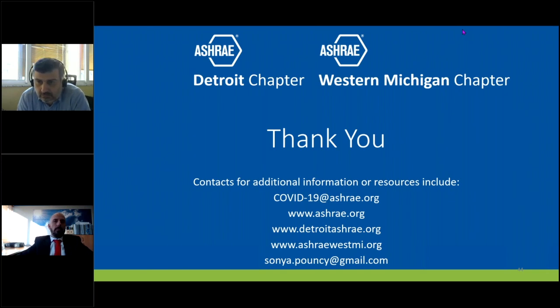If you can, field calibrate them, that would be good. You may reach out to, here in Michigan, we might use one of our test and balance or test adjustment contractors, who might be able to do something like that, or we would send out a calibration service provider to go and take a look at those. So calibrating is not something that you do often, right? You hope that the sensors will hold their calibration.